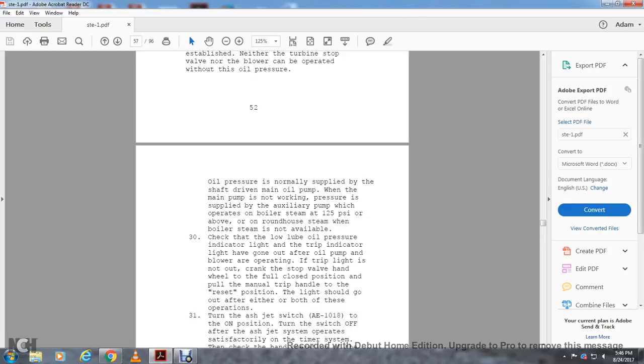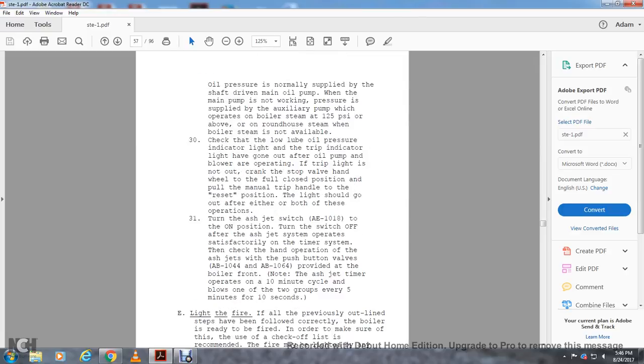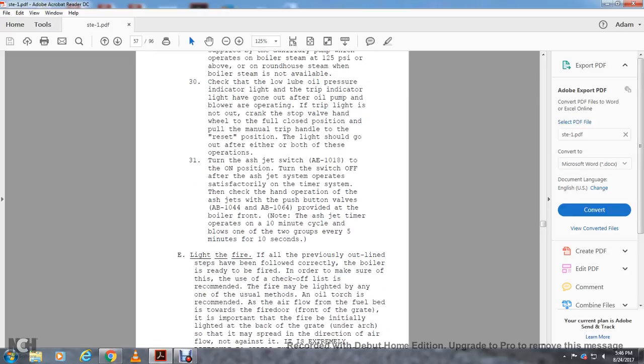The light should go out after these operations. Turn on the ash jet switch AE-1018 to the on position. Turn the switch off after the ash jet system operates satisfactorily. Use the timer system to check the hand-operating ash jets using push buttons AB-1044 and AB-1064, provided at the boiler front. Note that these ash jet timers operate on a 10-minute cycle and blow one of the two groups every five minutes, for 10 seconds.